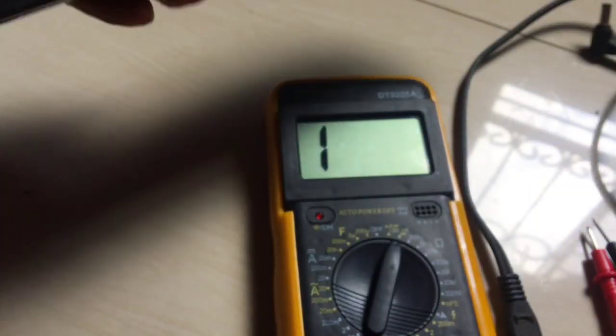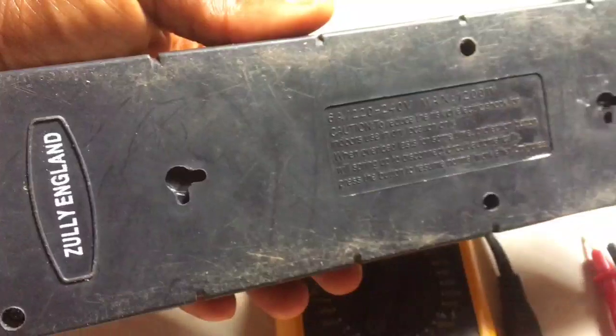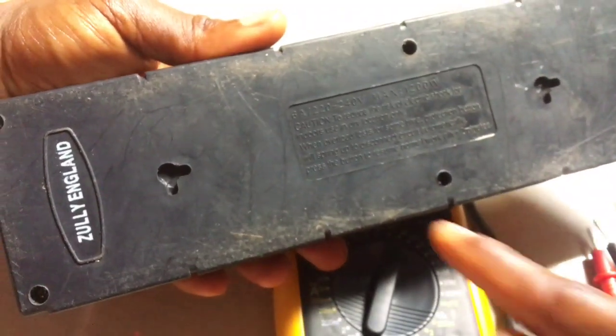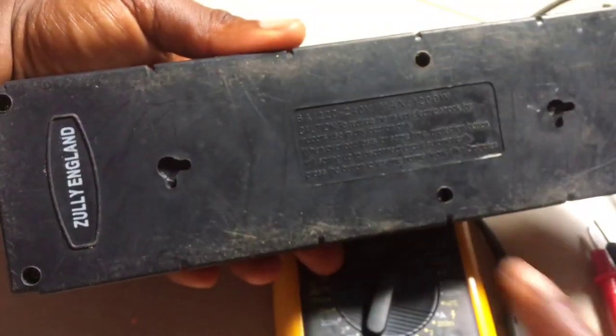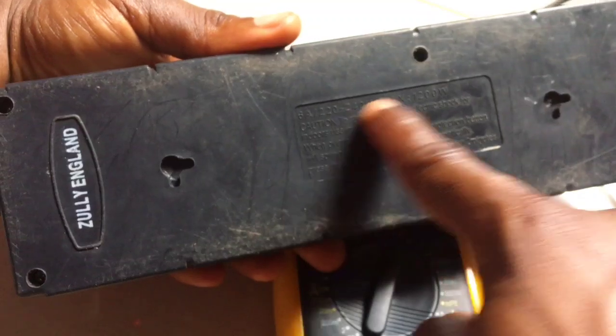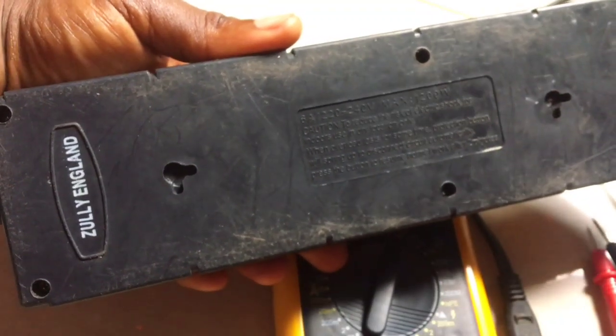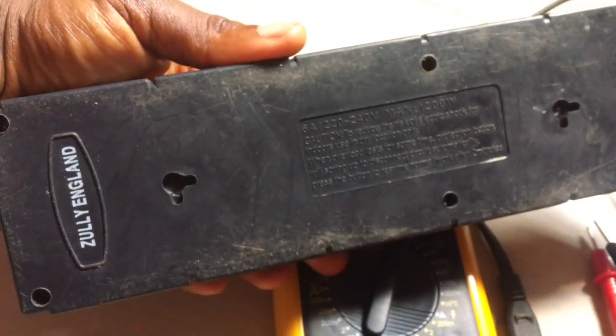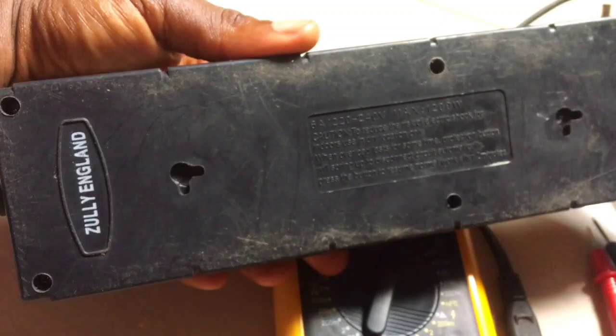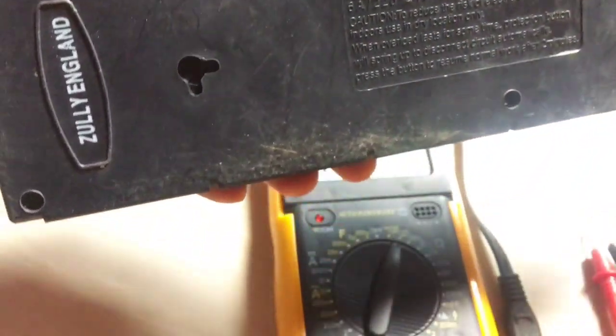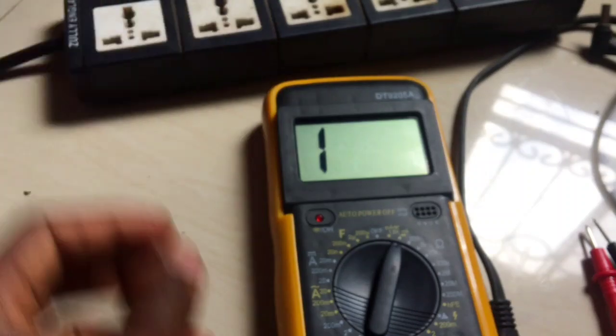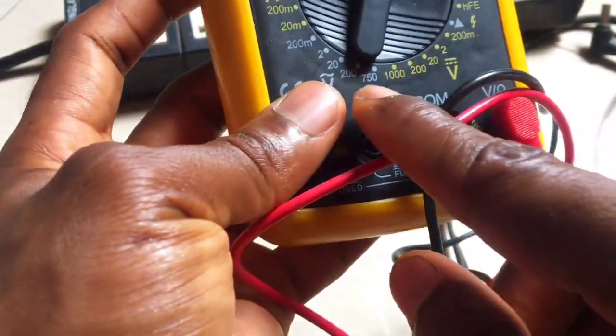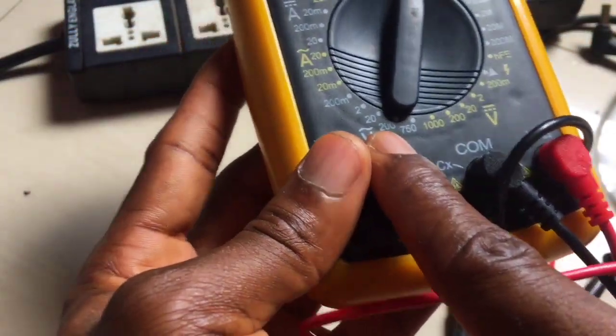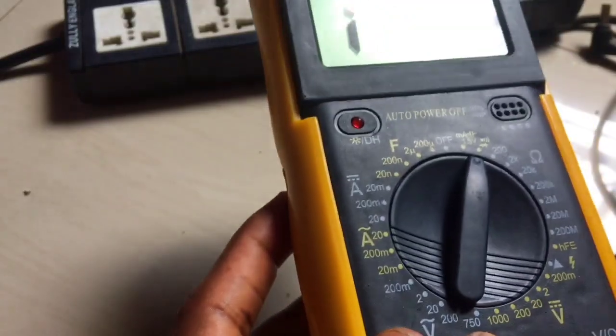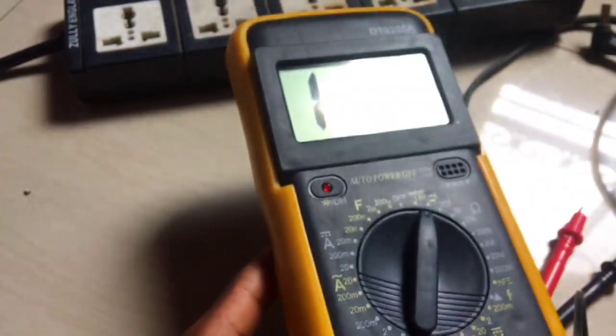So like this extension now, before I can test for voltage on this extension, you can read what we have here. First of all, it is 220 to 240 volts. I already know that from a wall socket, I'm getting AC type of electricity. So I already have in mind that I'm going to test for a maximum of 240 volts AC. On my meter, I don't have 240, the next highest value I have is 750, so it is safe to place it at 750.